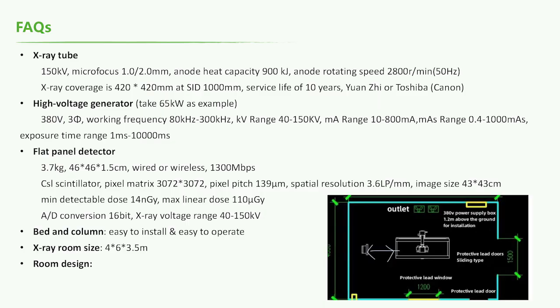There's a criteria about the X-ray room. The size should be 4 meters in width, 6 meters in length, and 3.5 meters in height. As you can see in the picture, I put an easy map here so you can figure out how the room is supposed to be designed and where the machines are supposed to be placed.